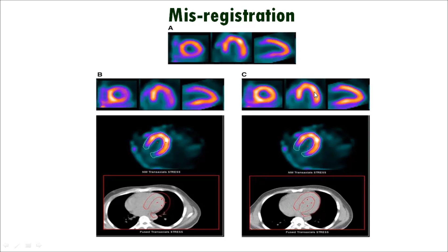So the co-registration test can be done by using a co-registration phantom. This is in case of GE, we are using this co-registration phantom. And if you don't have the co-registration phantom, the same test can be performed by using a SPECT phantom. So this is all about the artifacts produced in the SPECT or gamma camera due to errors in the quality controls.